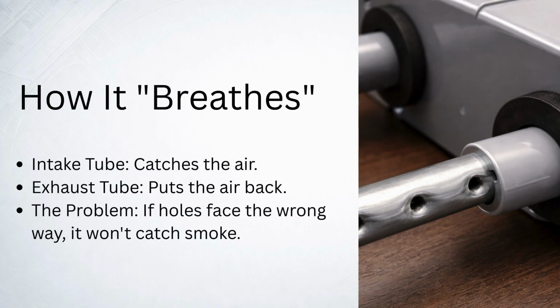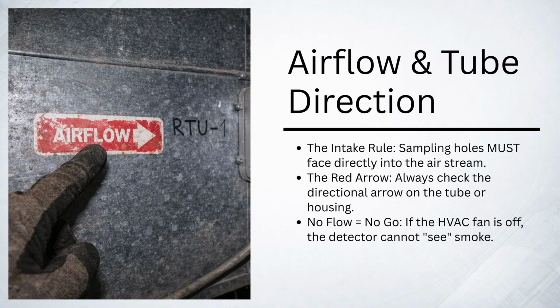Now, let's talk about the hardware. A duct detector has two pipes sticking into the airflow: the sampling tube, or intake, and the exhaust tube. The sampling tube has holes drilled along its length. It catches the air moving through the duct and forces it into the smoke chamber. The exhaust tube then pushes that air back out. Here is the critical part. The holes on the sampling tube must face into the airflow. I have seen countless installations where the tube was installed backward, meaning no air ever enters the detector. That device is useless.